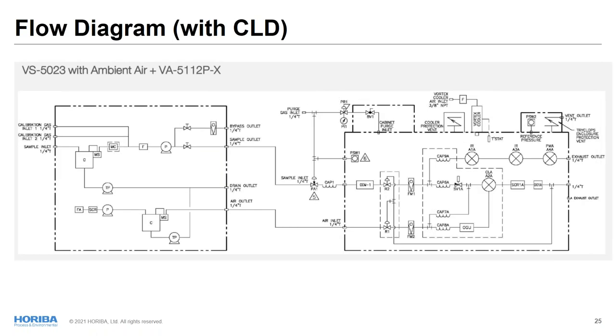All right, and this is another example of flowcharts showing the wall mount sample system and the wall mount VA-5000 with chemiluminescence CLD. The design of the sample system is a little bit different from the one for MPA or NDIR. Sample will be pushed from the inlet, and here is another line for the ozone generation. See this ozone generation. Because chemiluminescence needs ozone to react with NO, let me explain a little bit about the chemiluminescence principle.